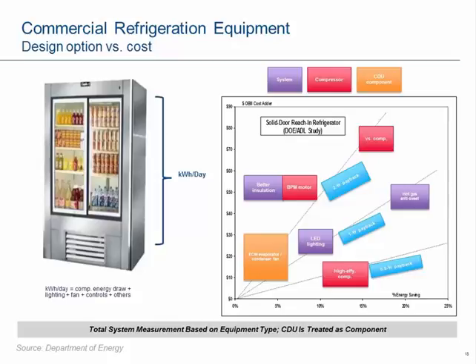It's interesting that a lot of people think equipment manufacturers would go right to insulation, better, thicker insulation, in order to reduce their heat load. As this study shows, that can be an expensive design option that doesn't get you the most bang for the buck. But as you'll see, with the very aggressive efficiency levels that are going to be required now and into the future, equipment manufacturers really do have to consider every design option.